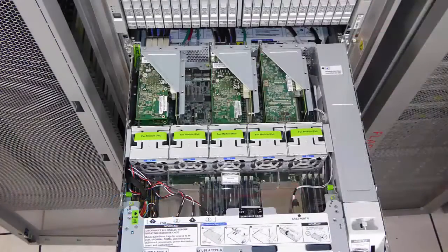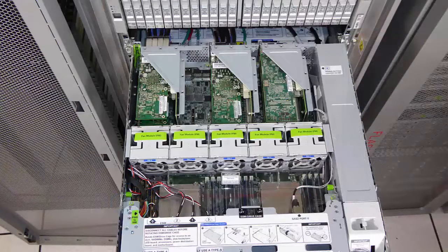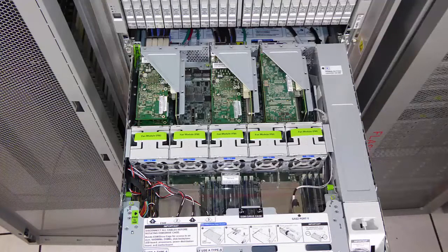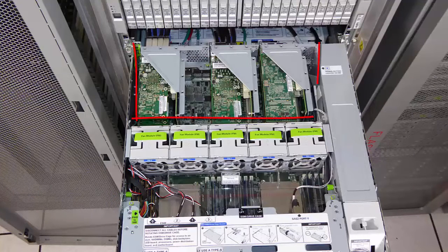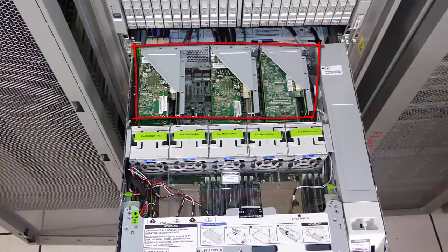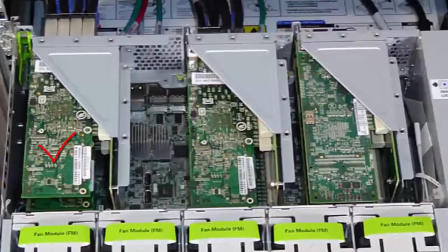In this procedure, we'll replace a controller HBA. Each of the three controller risers can accommodate two HBA cards. The HBA cards are located inside of the risers.